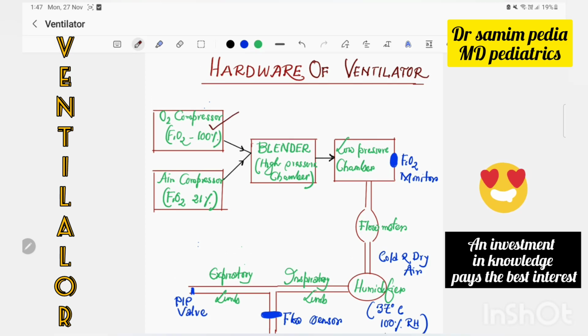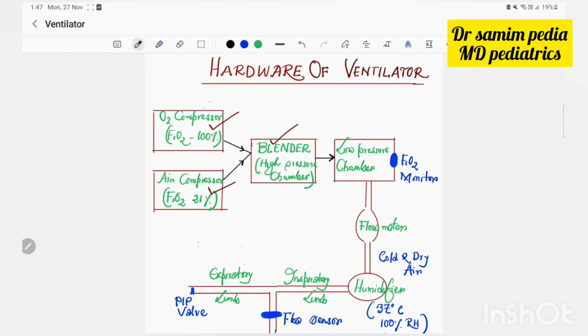This is the oxygen compressor, which contains 100% FiO2. This is the air compressor, which contains 21% FiO2. They are connected to a blender, which is a high pressure chamber. The blender mixes the oxygen and air and produces the required amount of FiO2. Then oxygen from the blender goes to a low pressure chamber where a FiO2 monitor is present to quantify the oxygen. Then air goes through a flow meter.